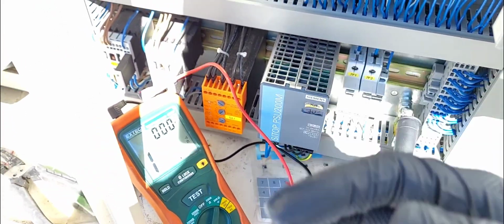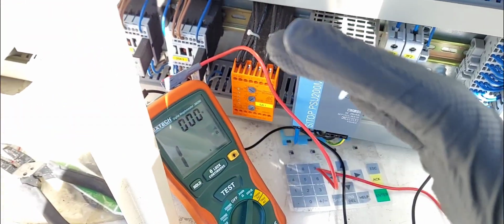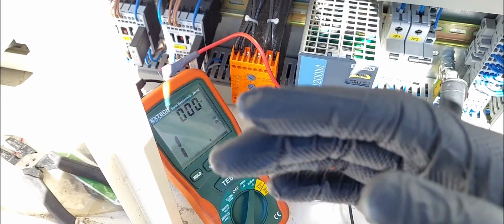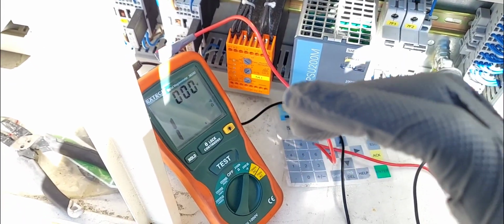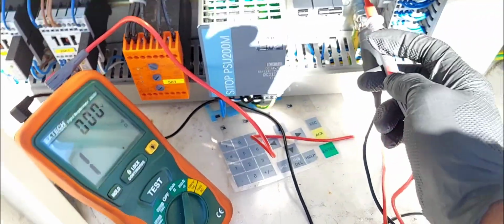They have sort of a paint, and over time sometimes this insulation over the copper wires of the compressor windings breaks down and they touch the chassis ground, and with that it draws a higher amperage, especially when the compressor gets hot. Right, so if you use a regular meter and test between your compressor winding and ground like so.